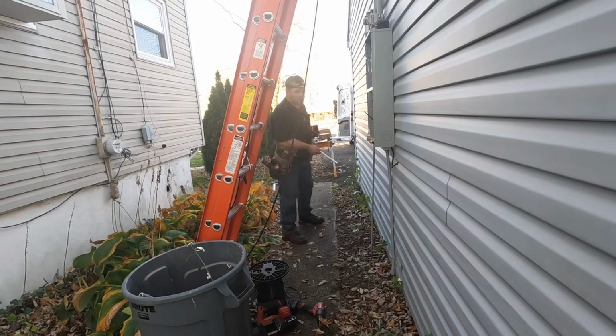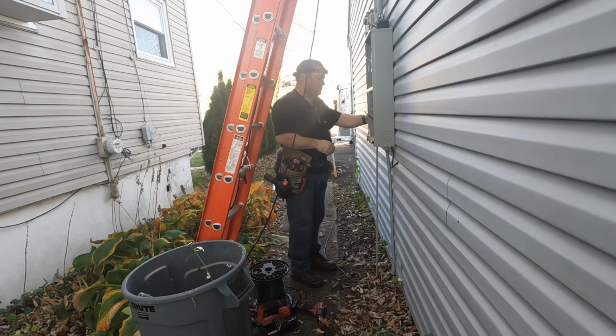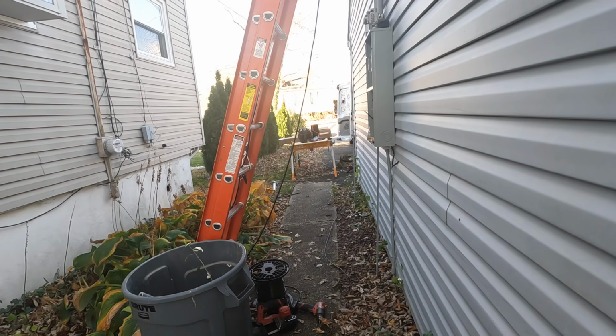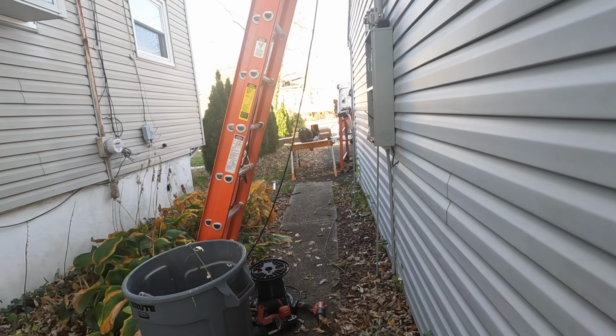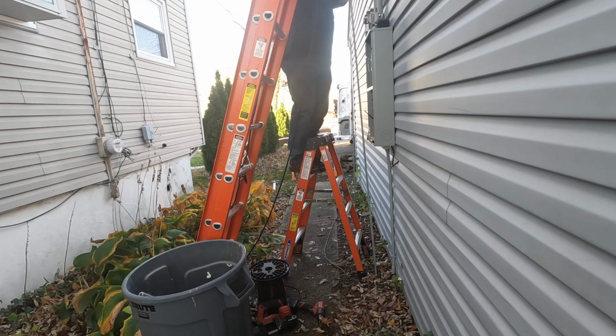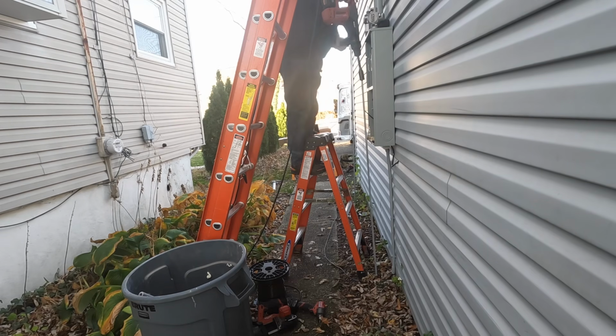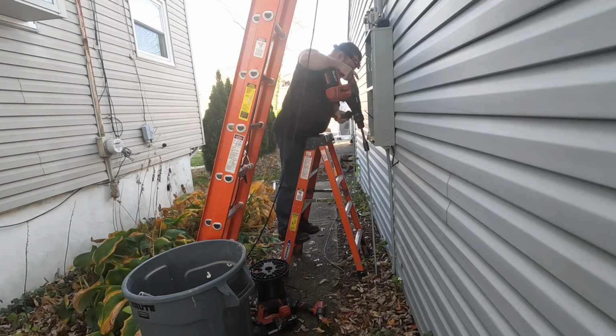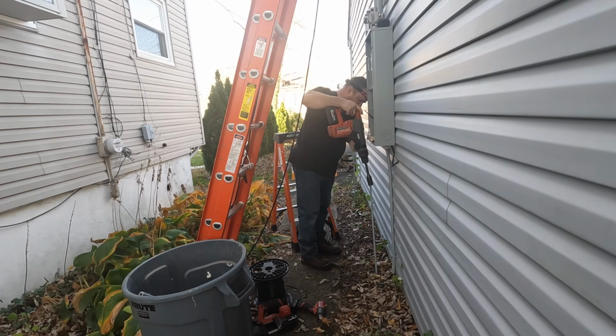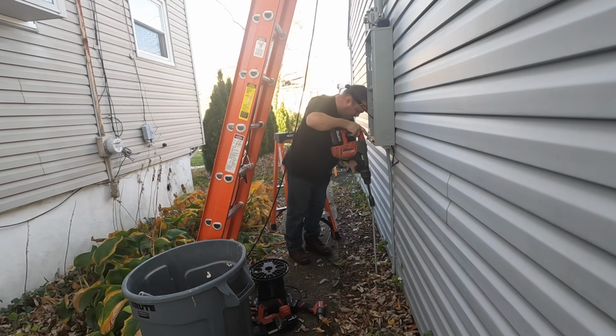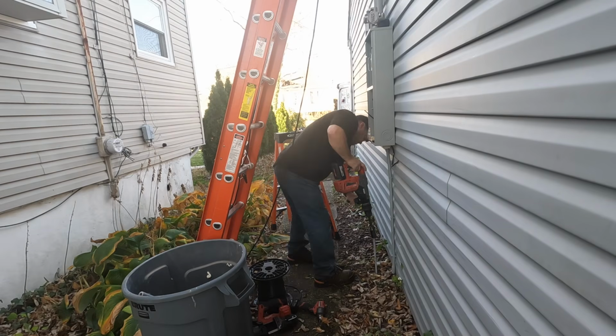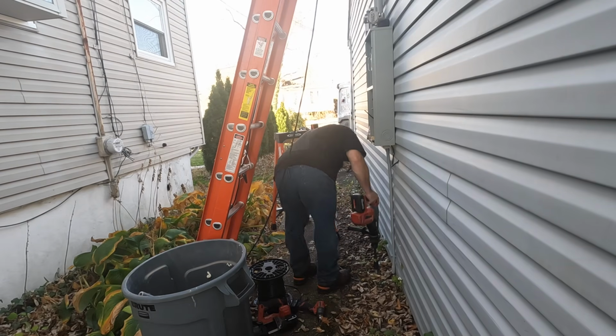If you look at table 250.66, you would see that 4/0 aluminum requires a number 2 aluminum grounding electrode conductor for the water main. Then if you scroll down to the same section, you'll see supplemental ground rods required, and that conductor, which I get questioned on, never has to be bigger than number 6 AWG. Now AWG stands for American wire gauge.